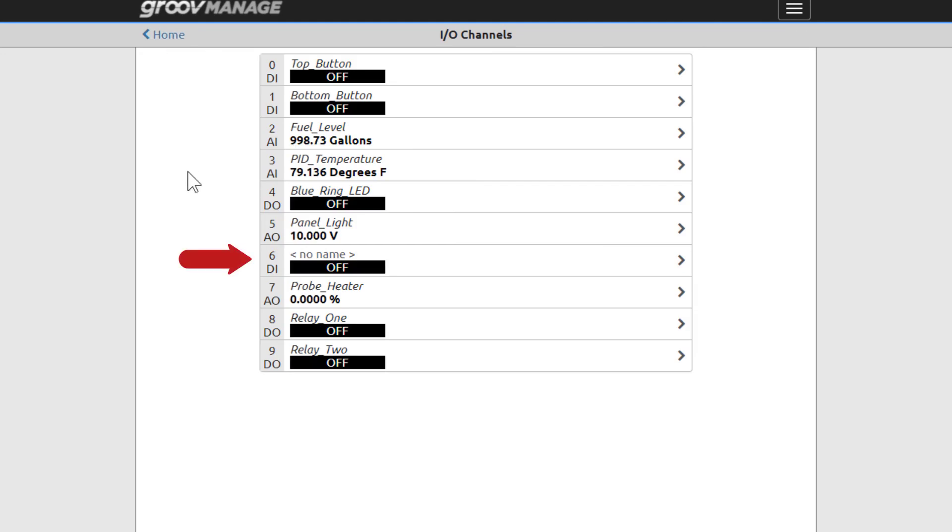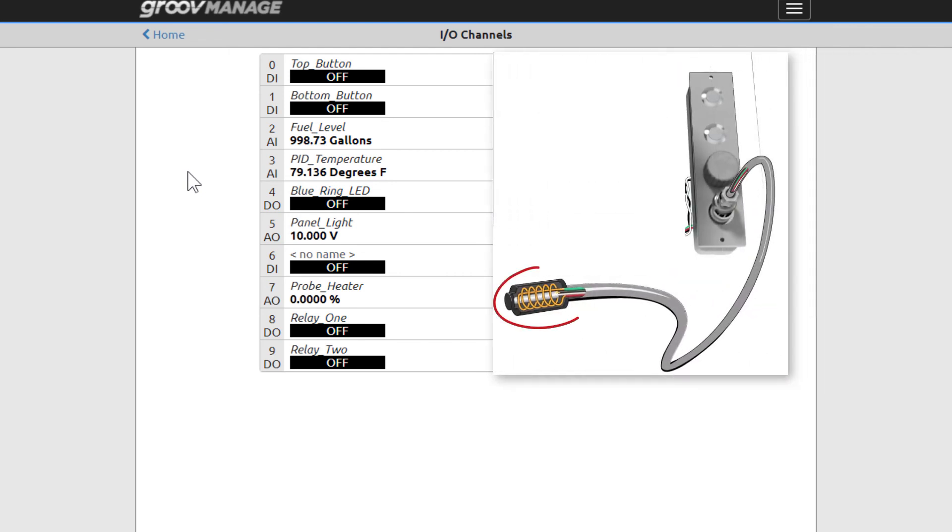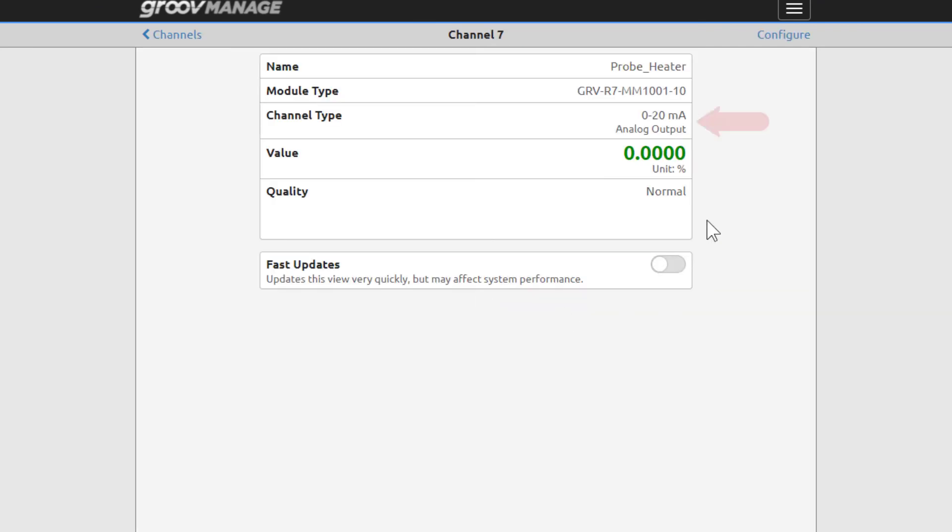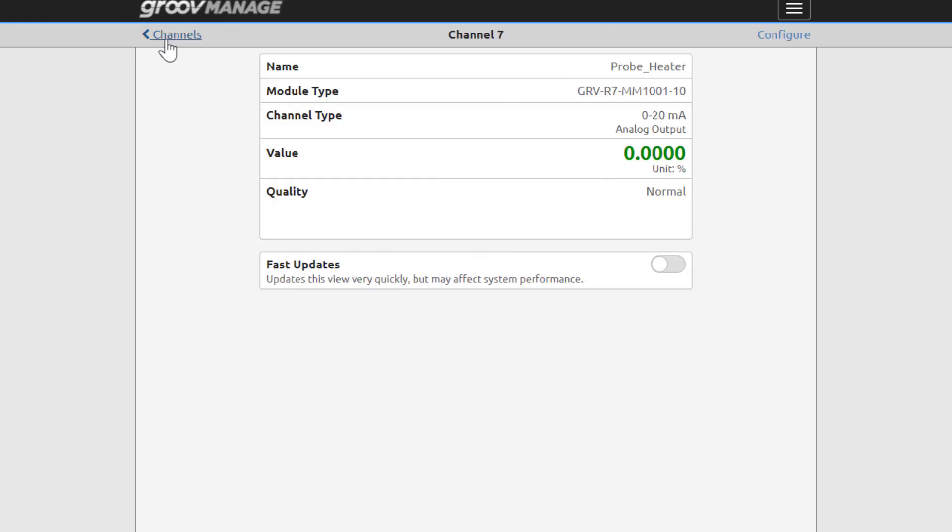Channel 6 isn't configured with anything, and by default is configured as a digital input. Channel 7, Probe Heater, is an analog output. This channel is connected to a resistor that was added to the tip of the ICTD probe. The probe on your Learning Center is actually part of a PID controller that's been set up. If the PID controller has to heat up to reach a desired set point, the PID will control the current output to this channel in order to heat up the resistor. This channel is scaled for a 0-100% output from the PID. We'll go more in depth about the PID in a later lesson. Click Cancel and then Channels.